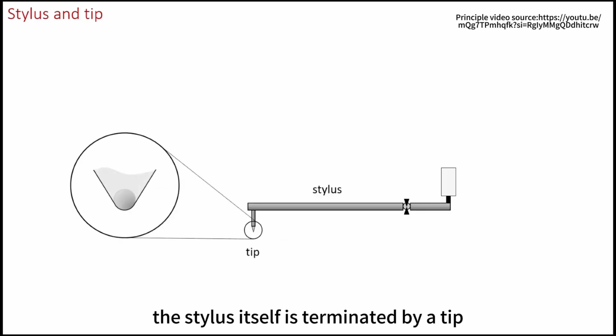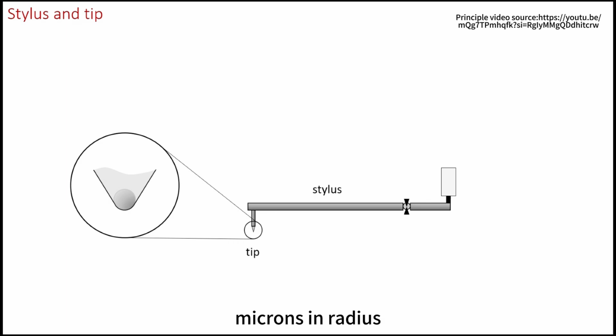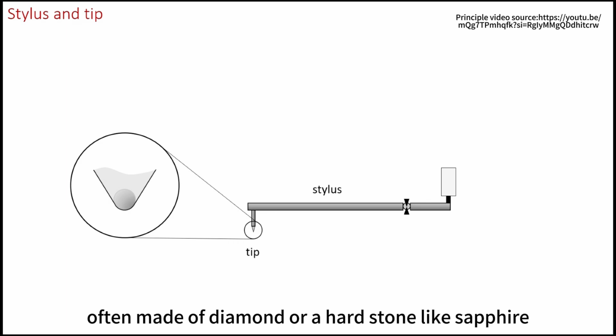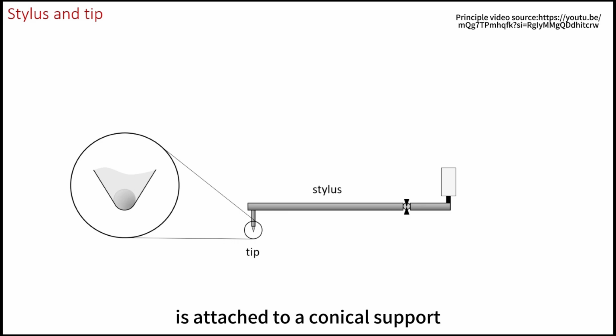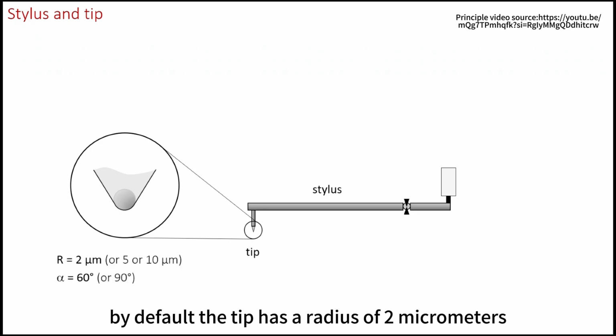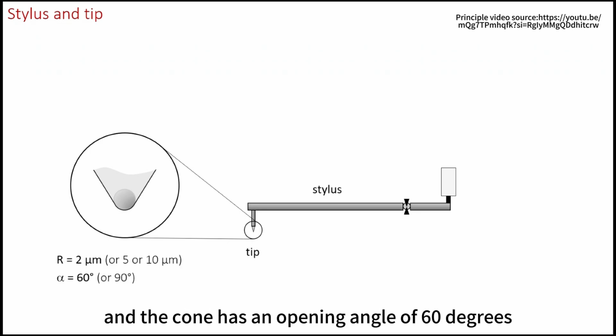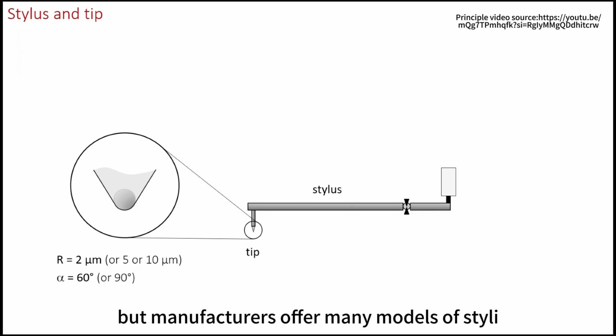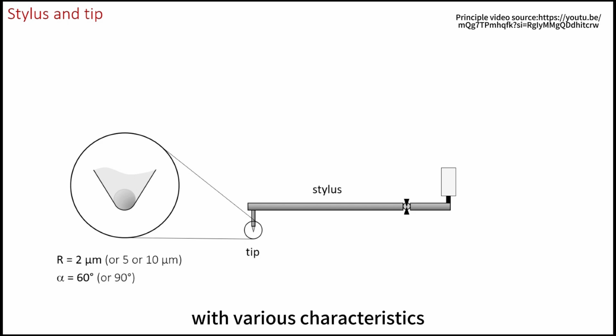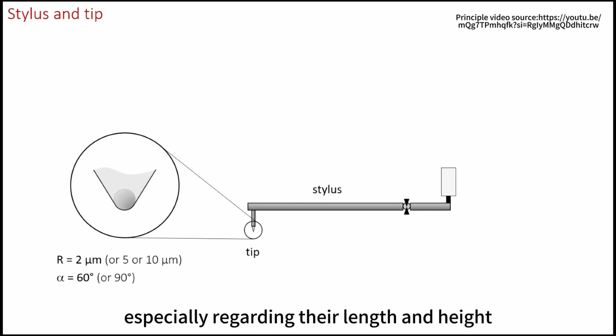The stylus itself is terminated by a tip, consisting of a microscopic sphere of a few microns in radius. This sphere, often made of diamond, or a hard stone like sapphire, is attached to a conical support. The whole constitutes a conospherical tip. By default, the tip has a radius of 2 micrometers, and the cone has an opening angle of 60 degrees. But manufacturers offer many models of styli, with various characteristics, especially regarding their length and height.